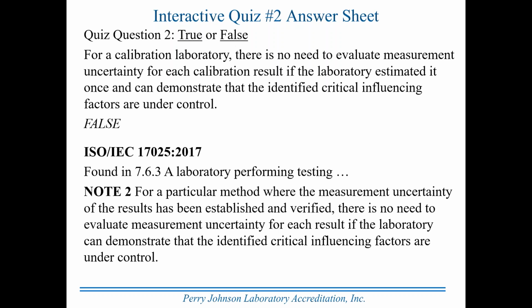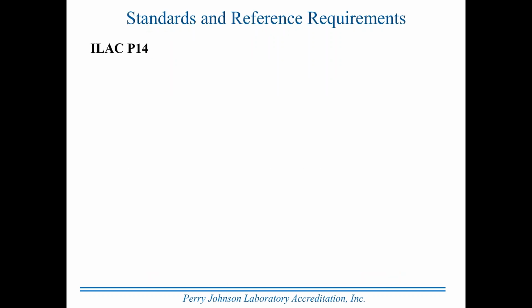A laboratory performing testing. Note 2. For a particular method where the measurement uncertainty of the results has been established and verified, there is no need to evaluate measurement uncertainty for each result if the laboratory can demonstrate that the identified critical influencing factors are under control. Testing laboratories only. I want to emphasize that. Be aware that Note 2 applies to testing laboratories only. And remember, calibration laboratories, every time a calibration is performed, an estimate of the uncertainty associated with the results is mandatory, has to be done.